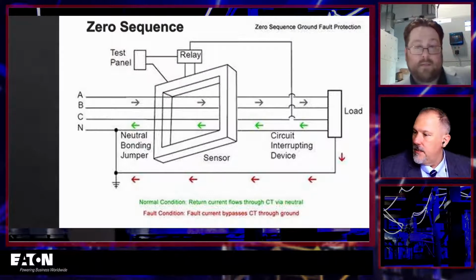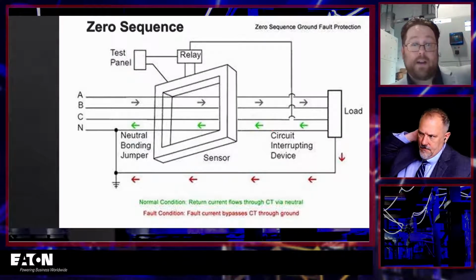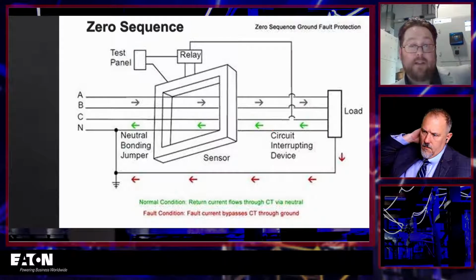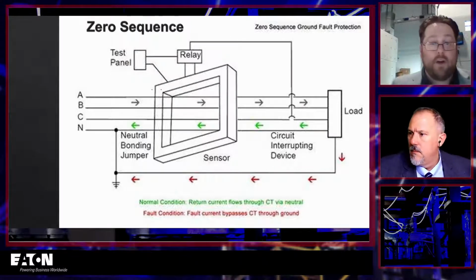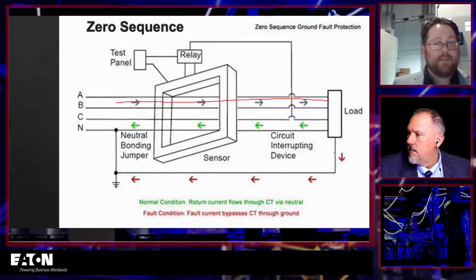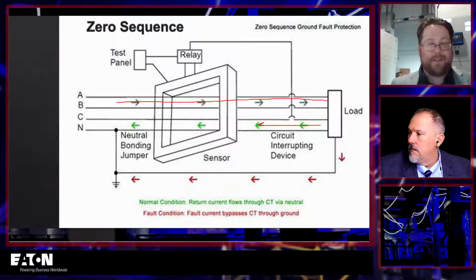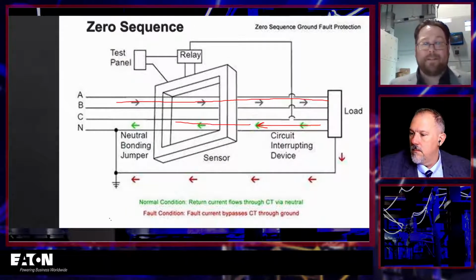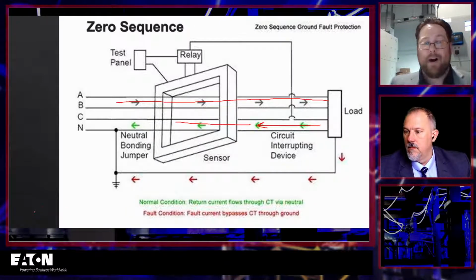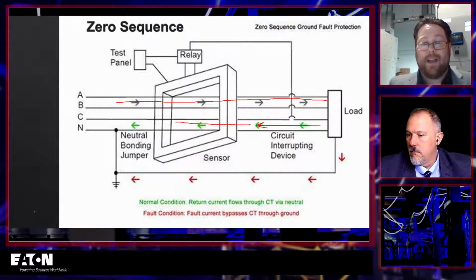So typically, current from phase A, the black arrows, flows through the load and comes back on neutral for a single phase load. Ultimately, the current flowing right equals the current flowing left, so the summation becomes zero. When you have a fault, though, you have this other path represented by those red arrows on the bottom through that ground, and that's what's going to be that ground fault.